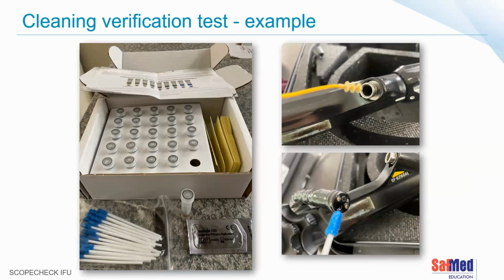Remember that we have to get a device completely clean before we can put it through the next level of processing. In the majority of cases for a flexible scope, it'll be high-level disinfection, but there is a call for sterilization on many of the operative scopes, and hopefully going forward we'd be able to adopt that too, so that high-risk scopes able to be sterilized are in fact sterilized. For that we'd need low-temperature sterilization. But before we do that, whether it's sterilized or soaked in a high-level disinfectant, or even sterilized with a liquid high-level solution, which is also possible and available in some settings, we need to make sure it's clean.